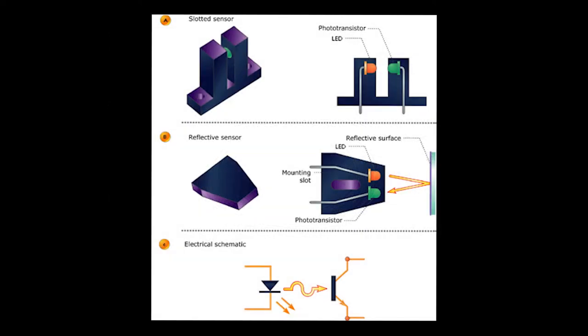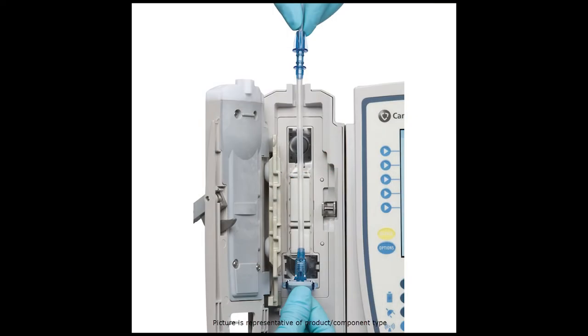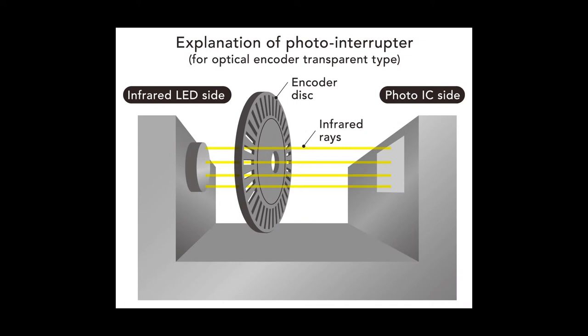Photosensors are used in a large variety of applications. They can be event detectors like a door open interlock, which shuts down the device or throws an error code when the door is not closed, or they can be something as simple as a consumable detector which detects when new consumables are inserted and readies the device for another set number of cycles. When matched to slits on a strip or on a disc, these sensors can detect linear travel speed, linear distance, rotational speed, or rotational distance.